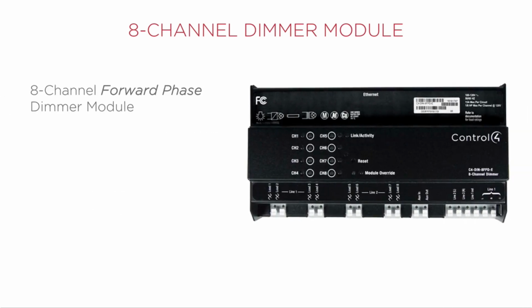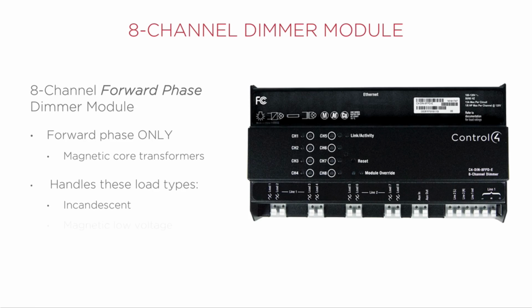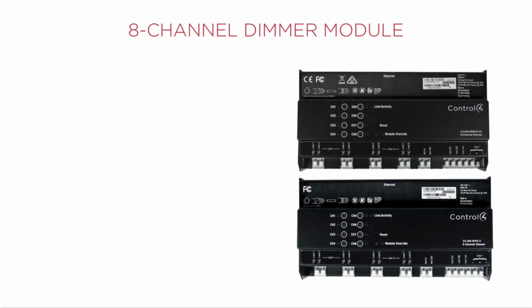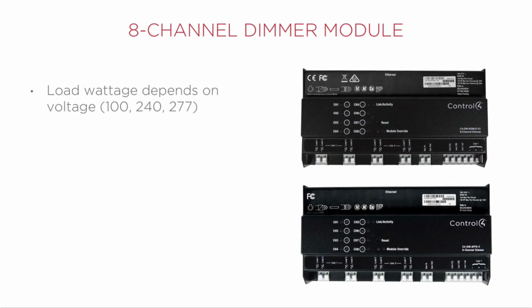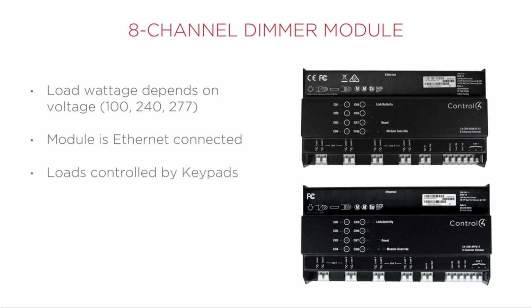The forward phase module only does forward phase dimming and only works with magnetic core transformers, and can handle incandescent, magnetic low voltage, and halogen. For either module, the load wattage depends on voltage: 100, 240, up to 277. The module is Ethernet connected, and the loads are controlled by keypads.